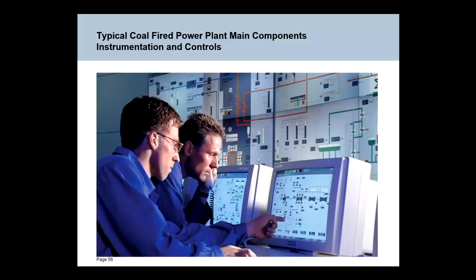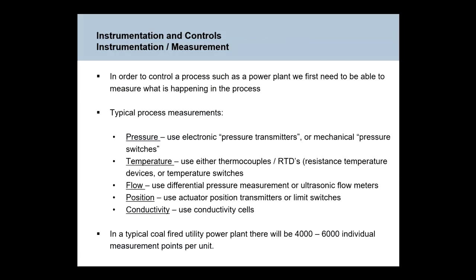Also in a power station, you will have a central control room in a modern power station, and the whole plant will be able to be controlled by screen-based controls by operators that sit in the control room. They don't need to go out unless something is broken, leaking, whatever else. Okay. And in order to do that, first thing is you have to measure all of the process variables out in the plant. You need to measure pressure, temperature, flow, position, and so on.